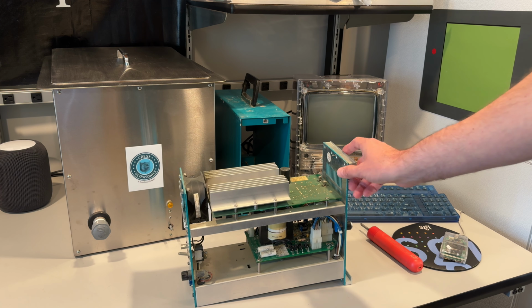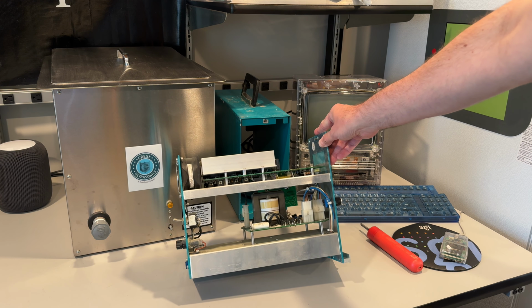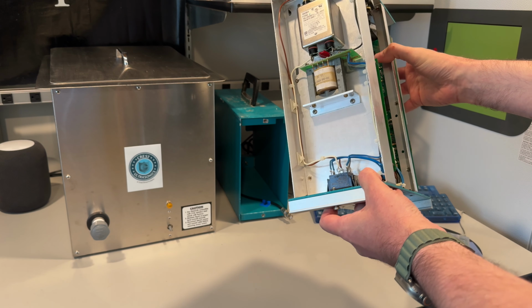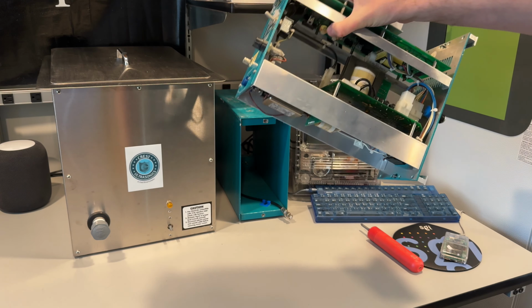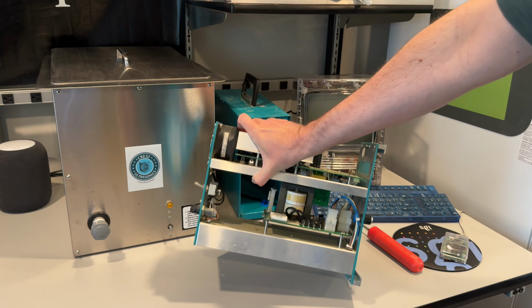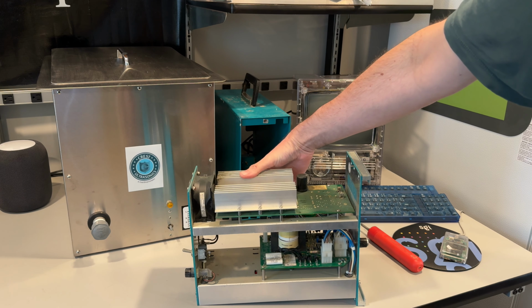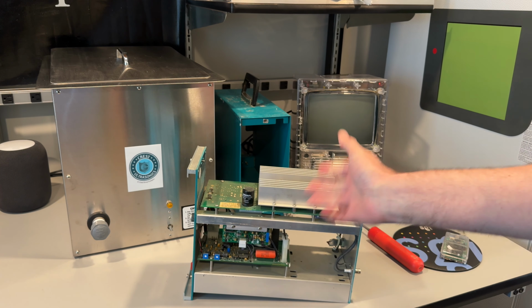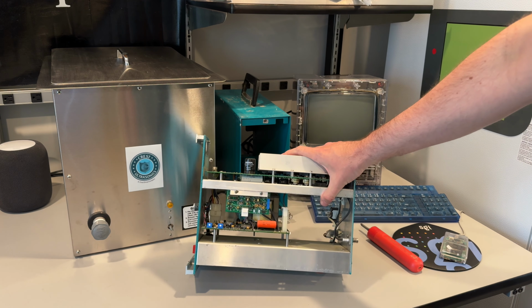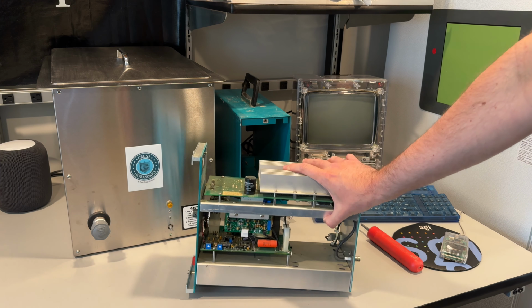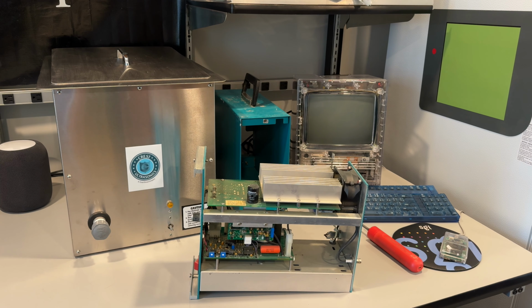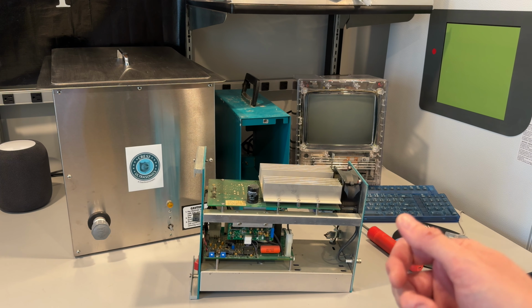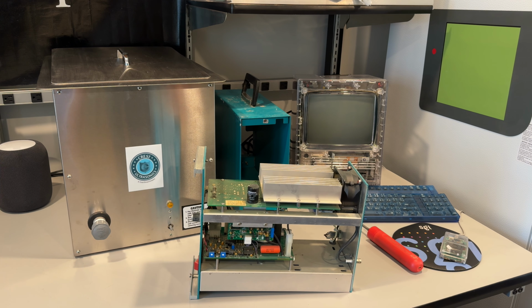Upper board and a lower board. So lower board is power supply stuff. There's a couple components below that, like a filter and a transformer, and everything else is on that power board above. And then a few other elements on the upper board, which looks like some MOSFETs and a little bit of circuitry for running the transducers, including a couple of trim pots, which the manual talks about, of like, this is how you would adjust to dial in the frequency of the transducers, but then it also goes on to say, don't do that yourself because you're not going to have the test equipment to verify everything is running as it should.